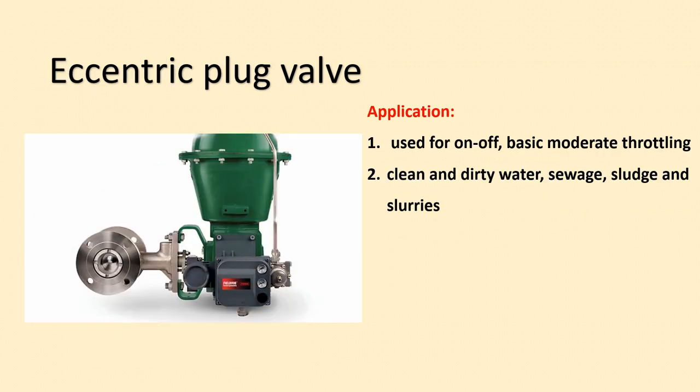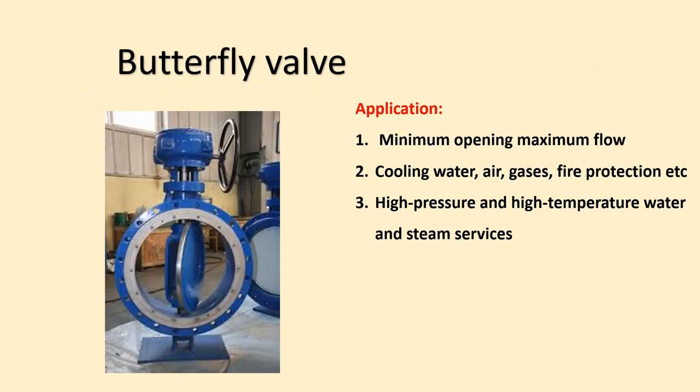Next, for rotary type valve bodies, we discuss the eccentric plug valve. From the diagram you can see that the valve motion is clockwise — it is a rotary type. This valve is basically used for on-off applications and offers only moderate throttling service. The best application of this valve is in abrasive fluids, sewage sludge, and chemical slurries piping.